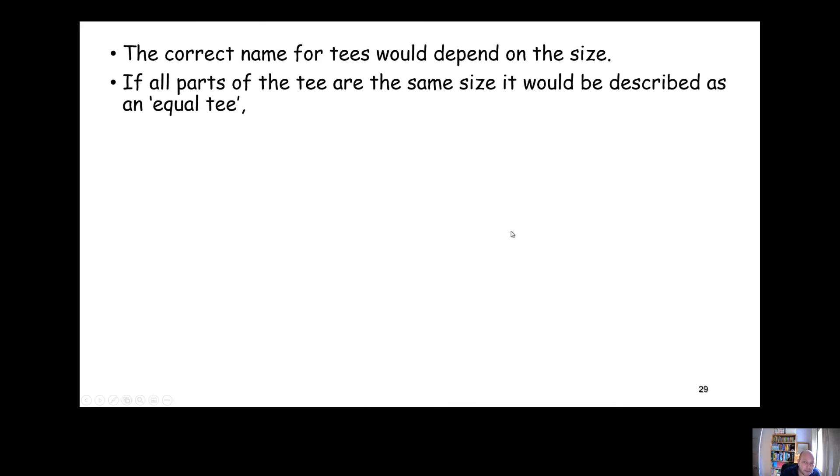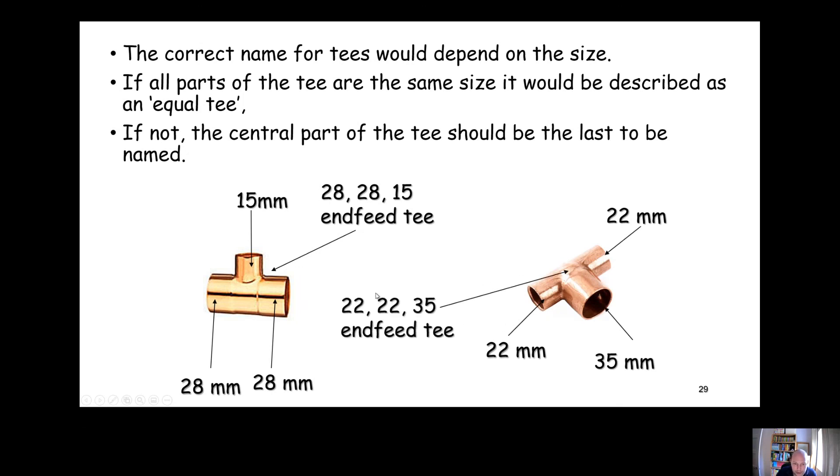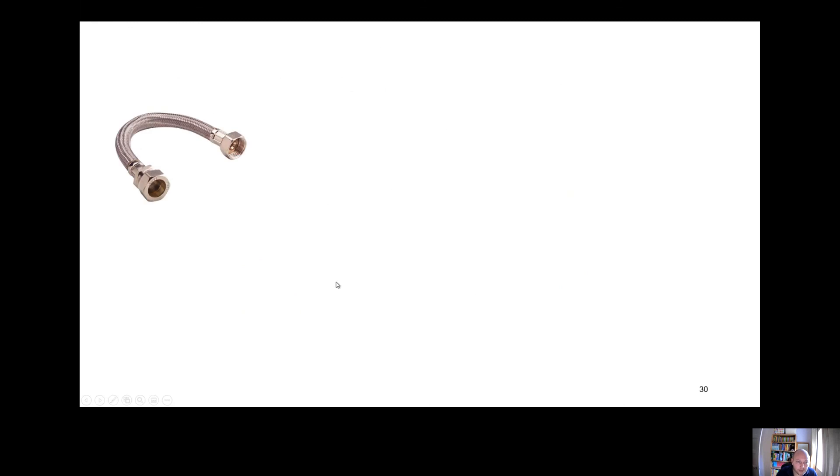Correct names for tees vary depending on their size. If all parts of the tee are the same size, it'd be an equal tee. So if all the parts were 15 mil, you'd call it a 15 mil equal tee. All the parts are 22 mil, you'd call it a 22 mil equal tee. If some of the parts are different sizes than the other, we'd always talk about the middle part, the central part of the tee, as the last thing we'd say. So this one, we've got two ends are 28 mil, the middle is 15 mil, so we call it a 28-28-15 tee, or a 28-28-15 endfeed tee in this case. This one we've got the two ends are 22 mil, the middle part's 35, so this one's a 22-22-35 endfeed tee.